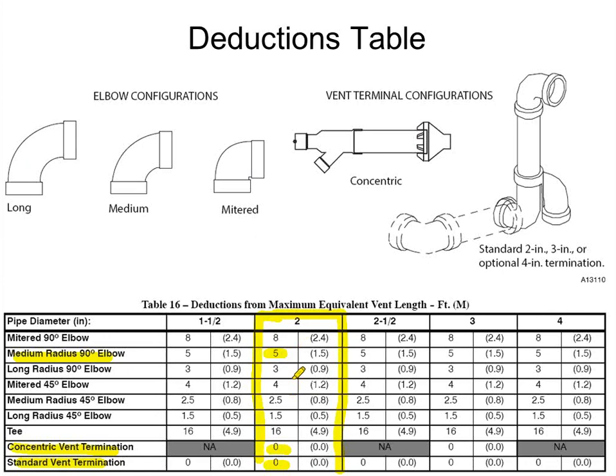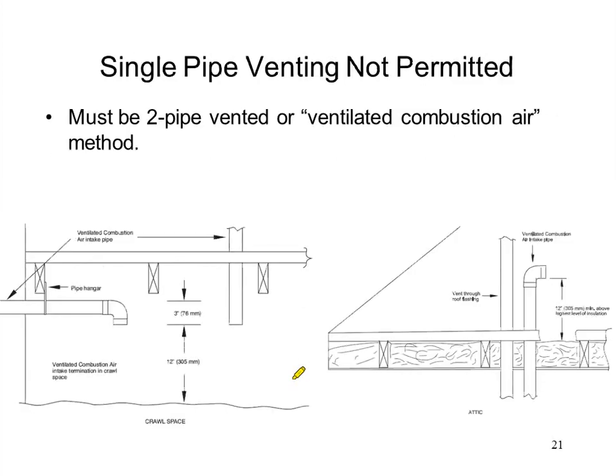Getting a lot of questions about the 2-pipe discussion. Right now we're specifically talking about the modulating gas furnaces, so the 987M from Bryant and the 59MN7 from Carrier. Those are the ones that must be 2-pipe vented or ventilated combustion air where you steal it from the crawl space or the attic, assuming those spaces are ventilated fully to the outdoors. Fully to the outdoors meaning I have soffit vents and ridge vents to allow air to come through the attic and on out. I cannot steal it from an enclosed attic.